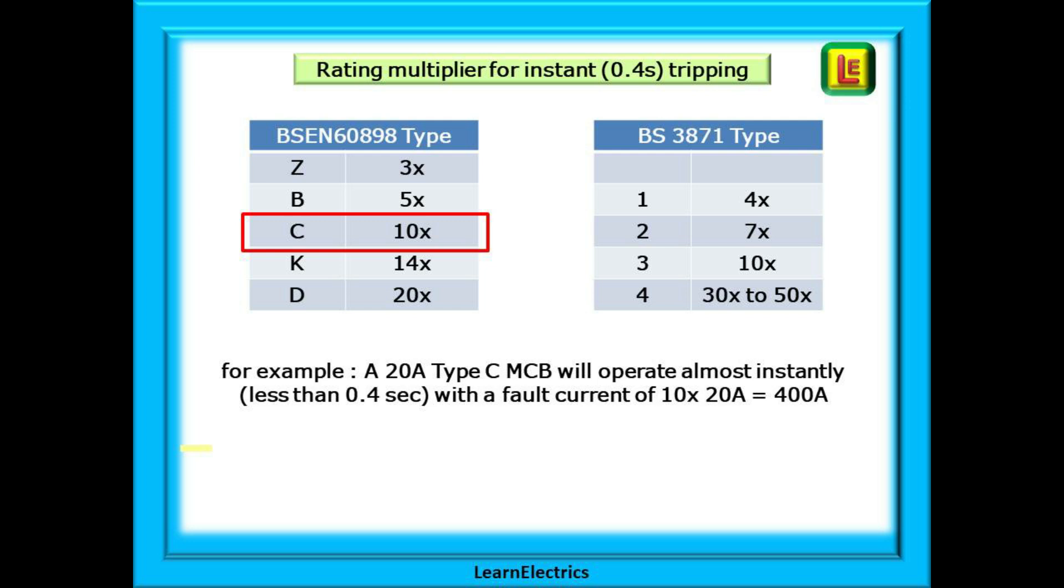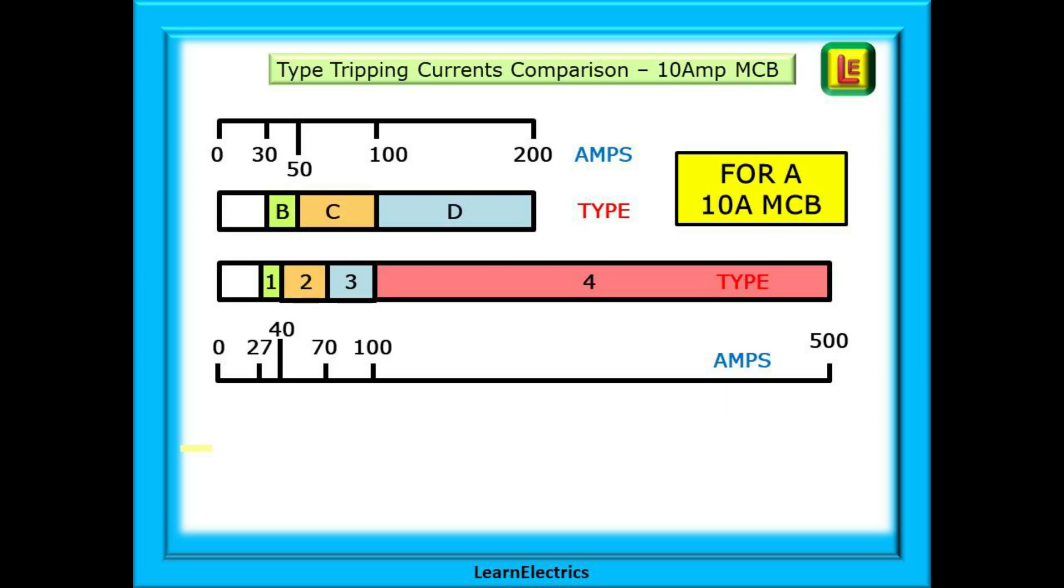For our example, a 20 amp type C MCB will operate almost instantly, that is to say in less than 0.4 seconds with a short or fault current of 10 times 20 amps which is 400 amps. This chart compares the tripping current of the 60898 types B, C and D with the tripping current of the 3871 types 1, 2, 3 and 4 and in this example we will use a 10 amp MCB for comparisons.